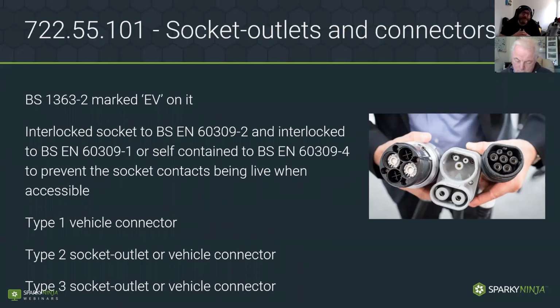We're seeing a number of examples coming up now where people have been plugging the vehicles in, and then after a period of time, there's excessive heating around the plug and socket, because the plug and socket is not really considered appropriate for that duration of demand. So they do manufacture specific sockets that are actually made for that to 1363. You could use a 60309-2.